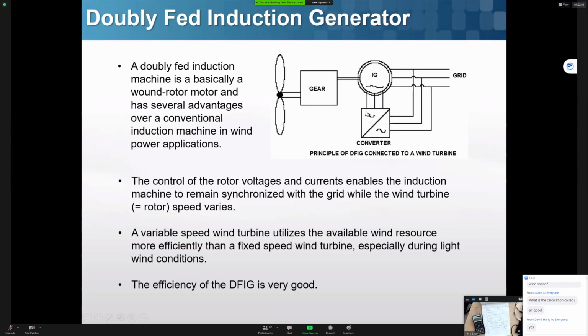Another major advantage, you probably don't have to know it. We're talking about different ways we can get this fixed voltage and frequency, but with this one we can use a smaller inverter down here. A different way is we don't use this doubly fed induction generator. We let the wind move the turbine at different speeds, so the generator rotates at different speeds and we generate what we call wild AC. Maybe you generate 400 volts at 30 hertz, or when the wind speed changes, you might generate 500 volts at 50 hertz or whatever the frequency. Basically, we don't care what's generated. We just put a kind of VFD inverter down here. We convert that AC into DC, then invert it back into AC to match the grid. So that's a different way you can do it.